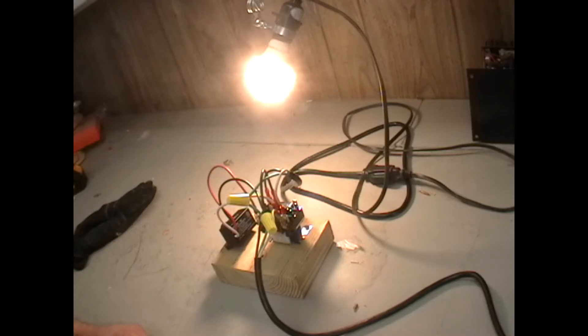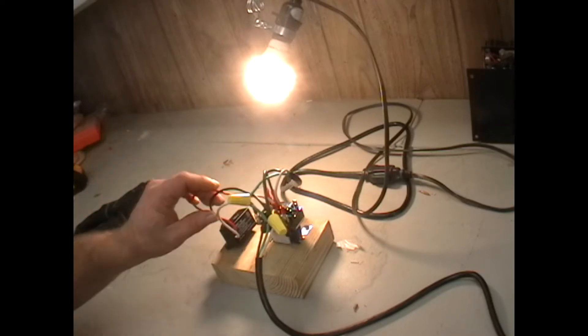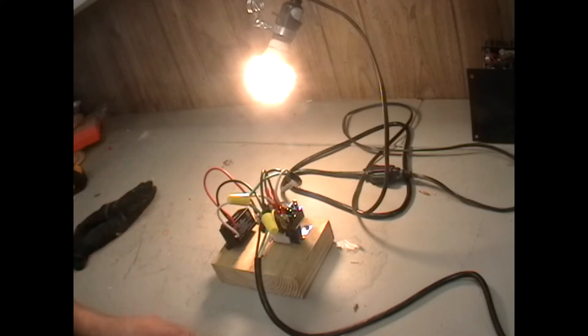Anyway, here's another relay that would do the same thing. We call this a little peanut relay. But you have to make sure that the coil on your relay is for 120 volts or 24 volts.